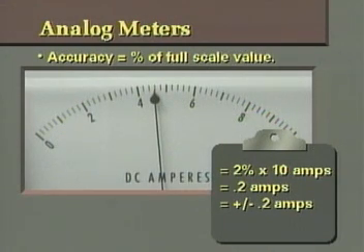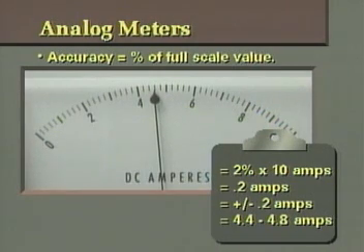For our reading of 4.6 then, the actual value could be between 4.4 and 4.8 amps. Since the accuracy of this analog meter is based on a percentage of the full-scale value, the variation of plus or minus 0.2 amps must be calculated for readings anywhere on the scale.